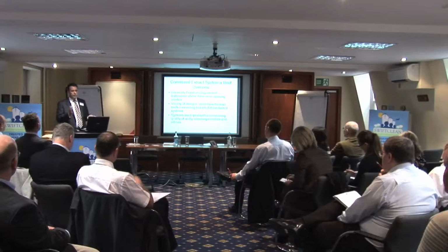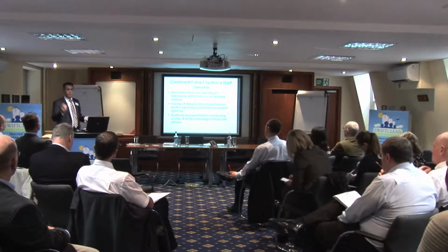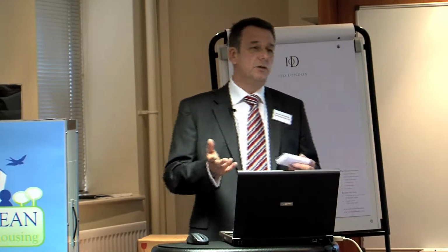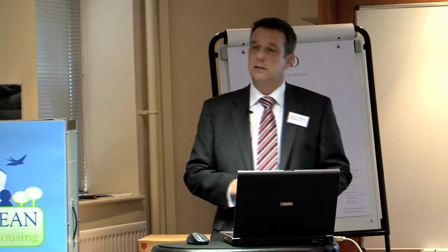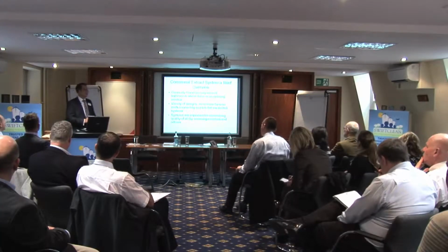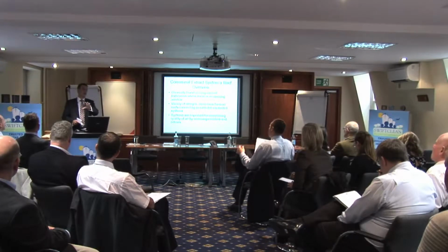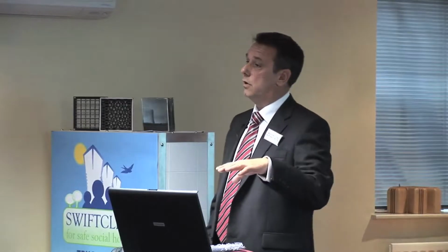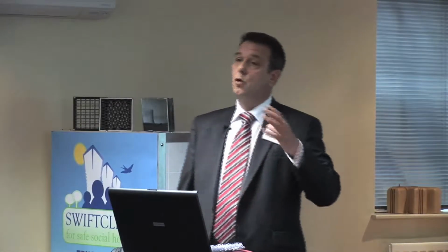There are various different types of ventilation systems in high-rise blocks and low-rise blocks, because we always think of social housing as high-rise, but it's not. The majority of social housing can be quite low-rise blocks, maybe 1 or 2 storeys high. The main difference between the two is that high-rise blocks normally only have 1 or 2 risers running up either side of the building, going to a central fan or central fans to discharge off the roof, whereas the low-rise ones tend to have a lot of smaller risers with lots of fans. So there's more maintenance in some of the smaller, lower-rise blocks than in the actual high-rise blocks.